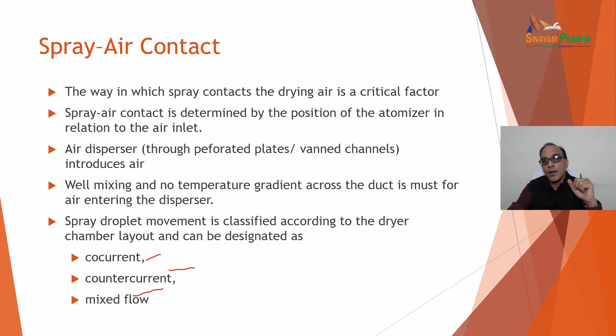Now, spray air contact, the drying chamber we are focusing on now. The drying chamber is either tall and slender, or has a large diameter with a short cylindrical height. The dimension selection criteria involves, number one, adequate volume to provide enough contact time between the atomized cloud and the heated gas. This volume is calculated by determining the mass of air required for evaporation and multiplying by the gas residence time, which testing or experience dictates. So on the basis of experience, you can go for designing the particular dimension of the drying chamber and ensuring the adequate volume.